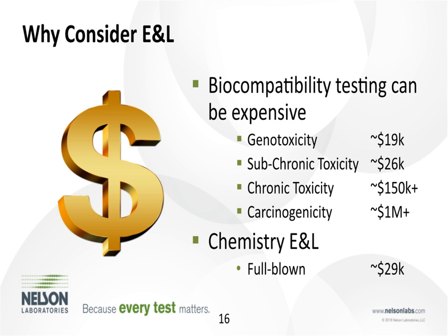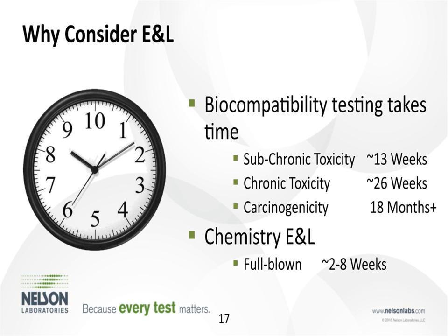Now, there are many reasons to consider extractable leachable testing. We've got biocompatibility testing, and I've listed some values there so you can look at a comparison. Chemistry extractable leachable testing can be considerably cheaper. Also, a lot of the biocompatibility testing can take several months, where chemistry in general can be done quicker. Now, I do want to mention that you need to allow some time on the back end after the results are received for that toxicological risk assessment.